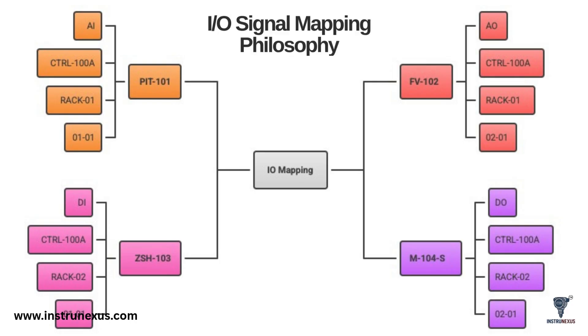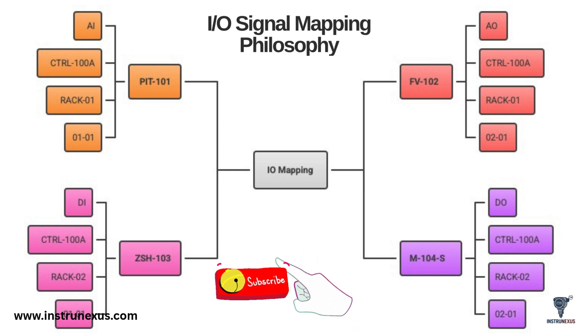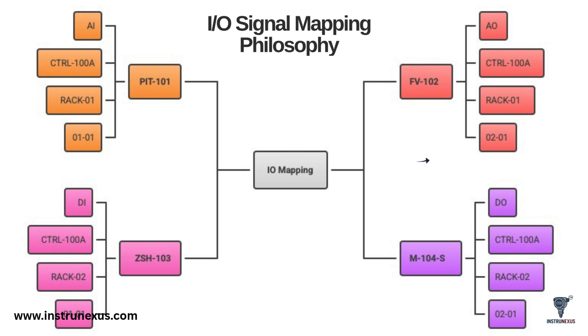Let's look at a practical example of an IO List to see how it all comes together. This table shows four different tags mapped to a single controller. First, PIT-101, a pressure transmitter – its IO type is AI (analog input). This signal is wired to controller CTRL-100A, RACK-01, channel 1 on slot 01. This is how the DCS reads the reactor pressure. Second, FV-102, a flow control valve – its type is AO (analog output). The DCS sends a signal from slot 02 in that same rack to tell this valve how far to open or close.